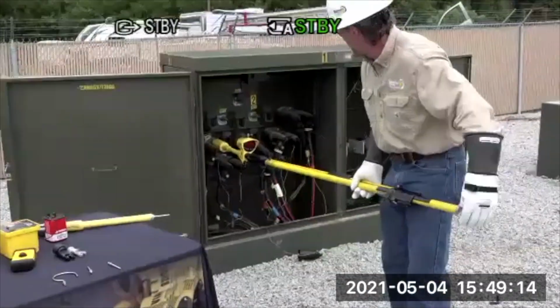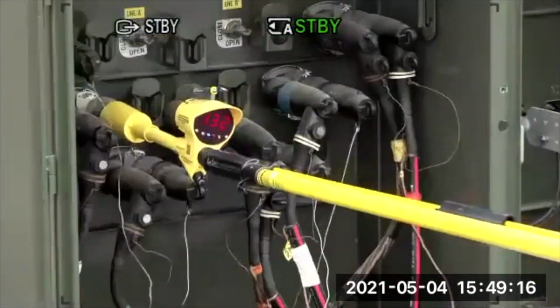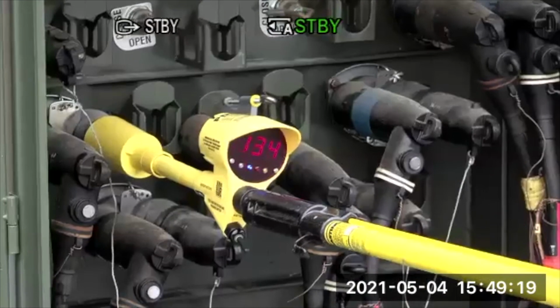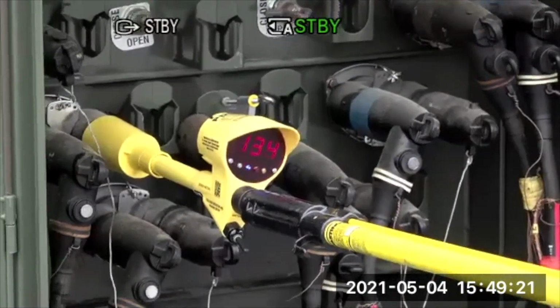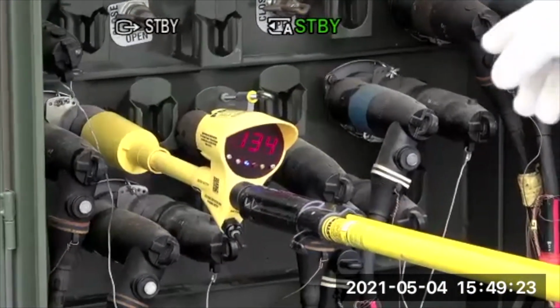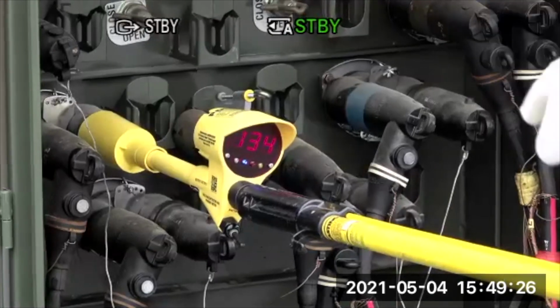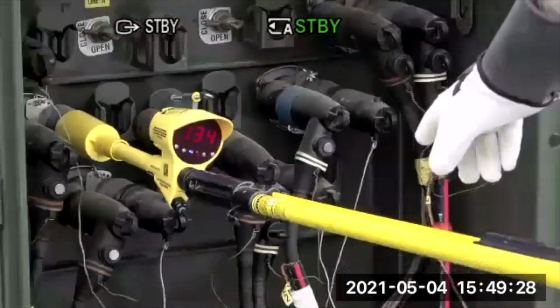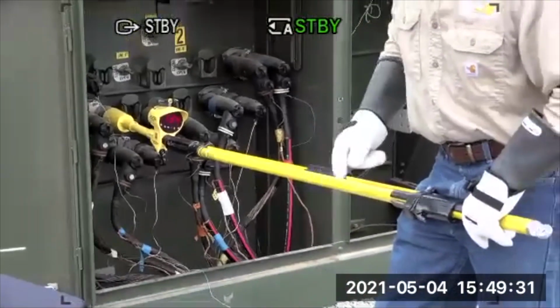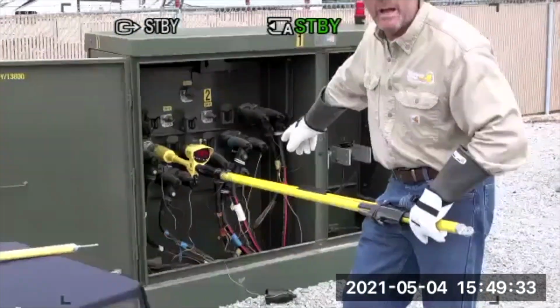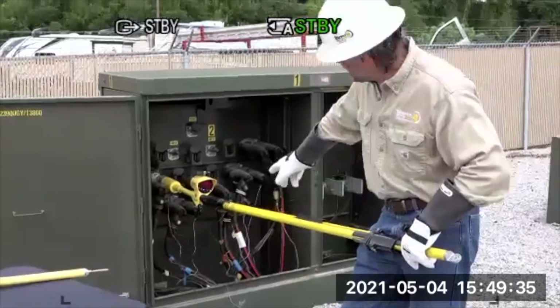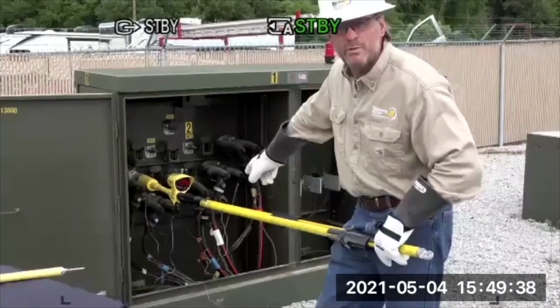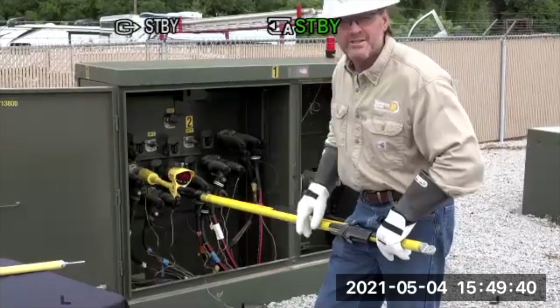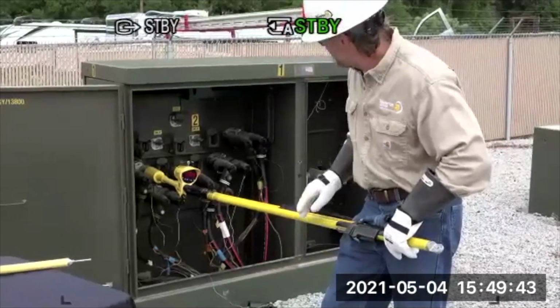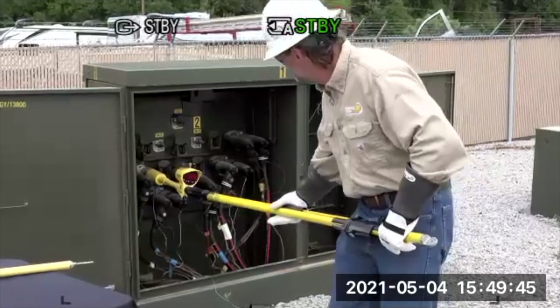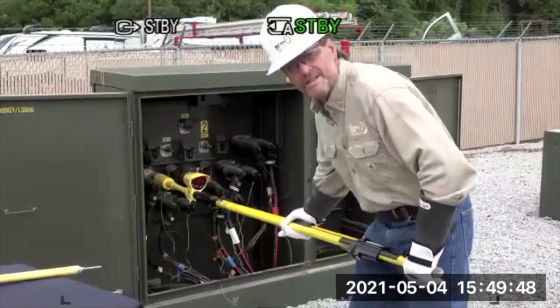You want a blue phase there? Okay, so we're referencing a blue phase. So you can see that we're on the white phase and we're about 120 degrees out, and we got a blue light. So that's telling us that the sequence is blue, white, and red. That's our sequence here. That's on about 14,000 volts.